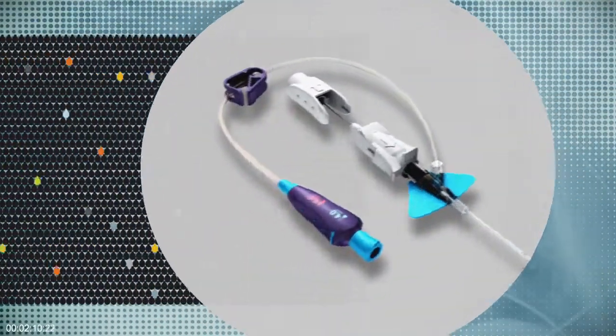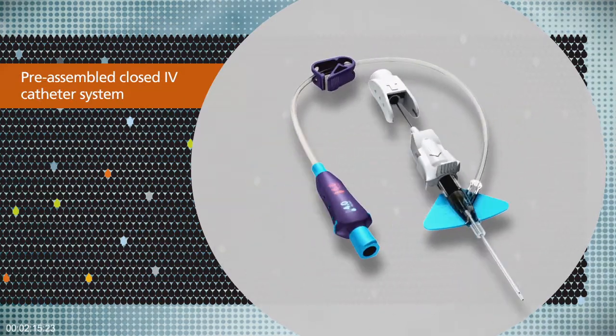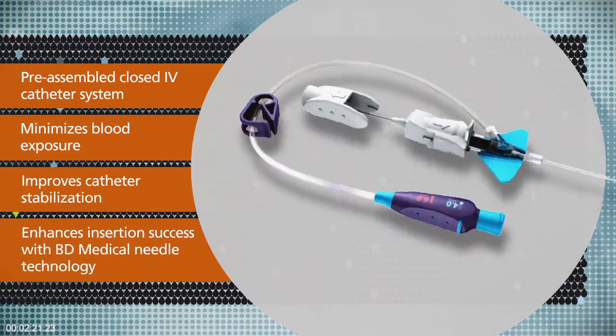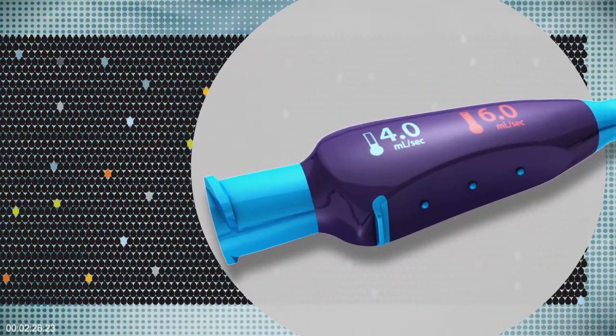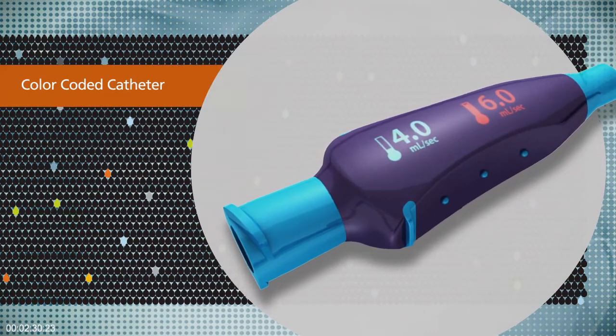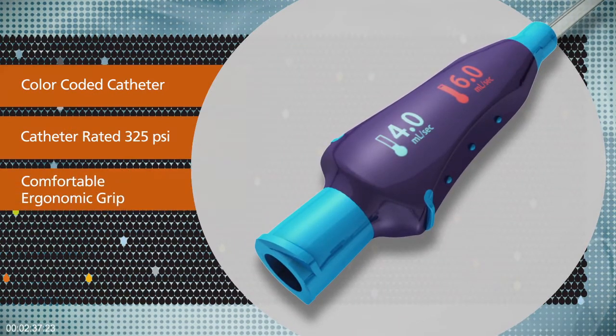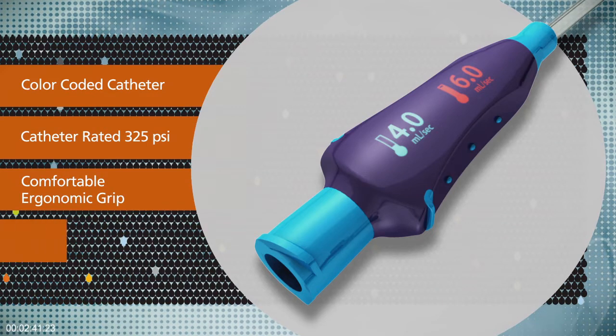In addition, BD Nexiva Diffusics is a pre-assembled closed IV catheter system that is designed to minimize blood exposure, improve catheter stabilization, and enhance insertion success with BD InstaFlash needle technology. The catheter is color coded to indicate power injection compatibility, and it is also the first IV catheter rated to 325 PSI.